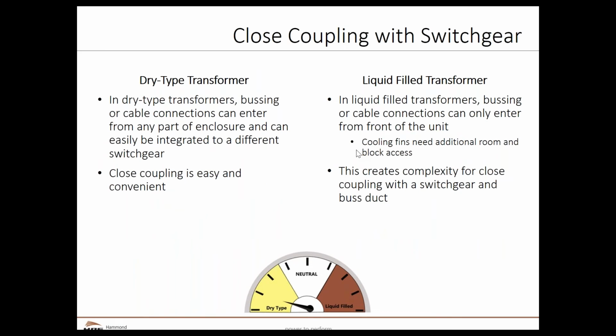Close coupling to switchgear, dry type has some advantages. You can come in from the top, bottoms, ends, sometimes from the sides. We can close couple in a lot of different ways and configurations. With liquid filled, typically I have a wiring compartment in the front, and I can only come in from a couple of directions from that front mounted wiring compartment. I am much more limited in how I can bring in cabling or busing.